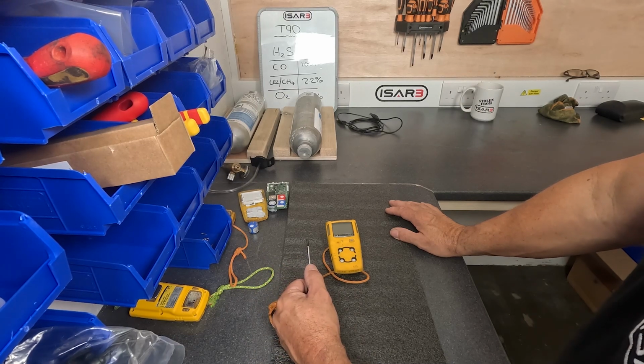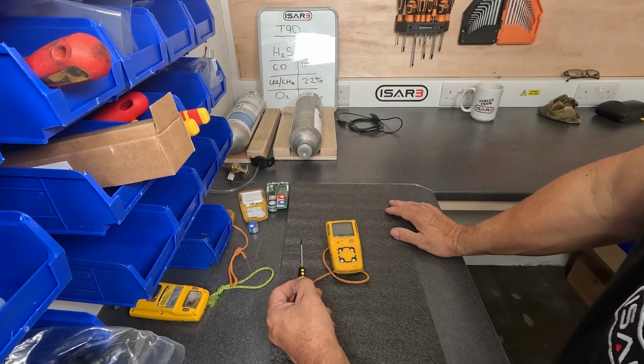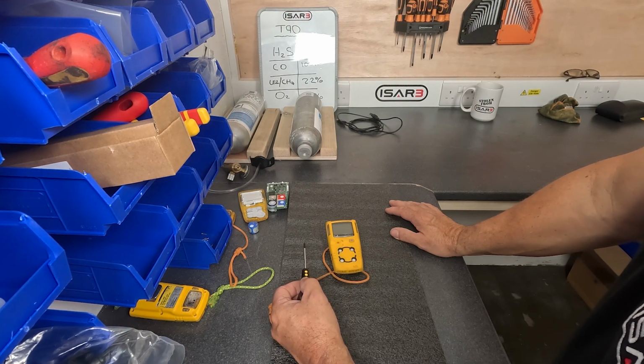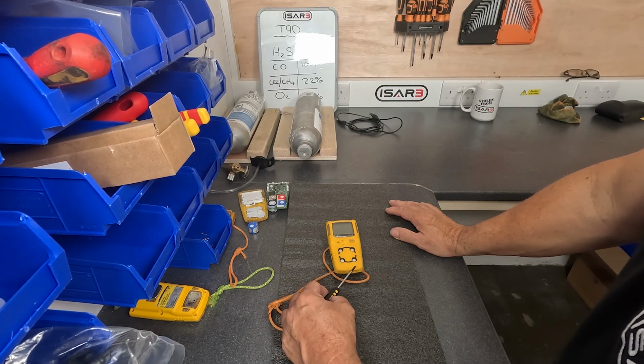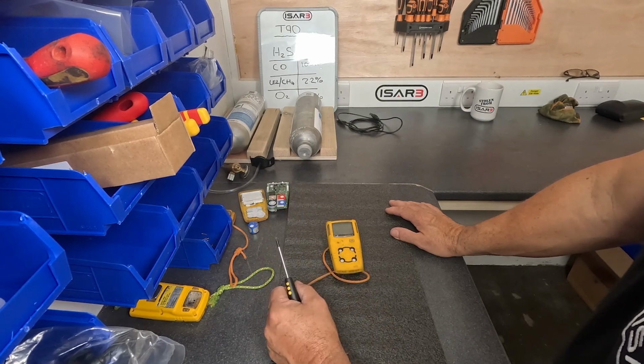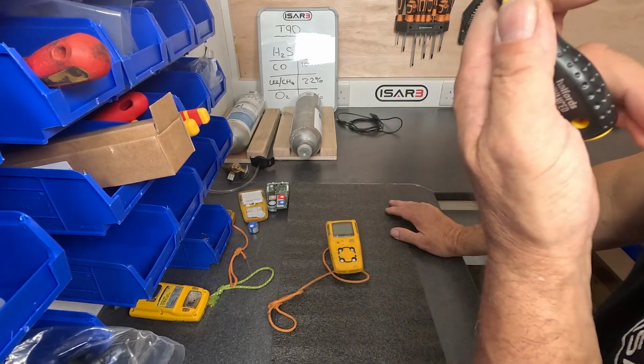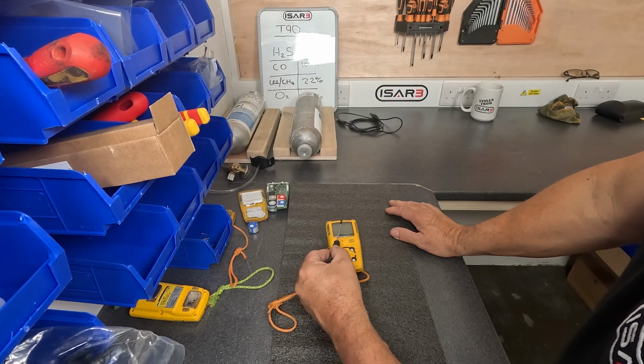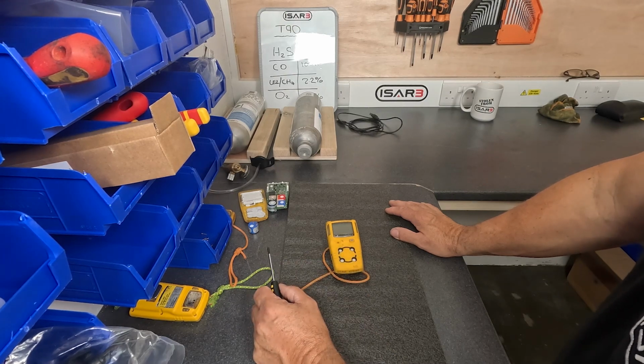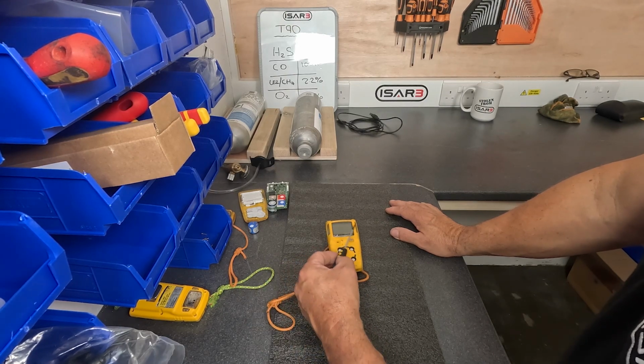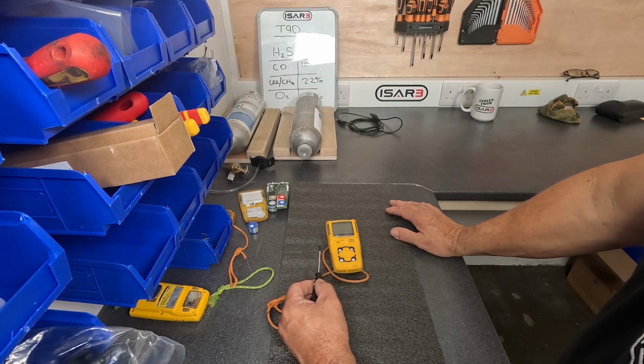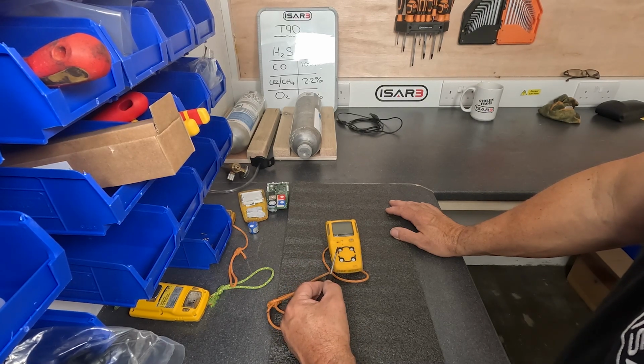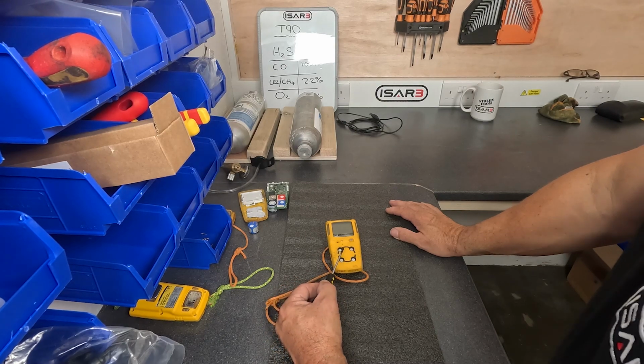And again, you can show the students an example of that if one of your gas sensors is a little bit off. All right, we record the bump tests, and you should be encouraging students to do a bump test and then to record it. Some organizations just put the date and the gas detector number and then just pass. All right, what we have is a sheet on ours, and so they'll actually write in the numbers that they see on the screen when it's stabilized. So we've got a complete record of how this gas detector is performing on the day when it was bump tested. All right, and I think that's good practice to show students that and encourage them to do it on each morning of the class.